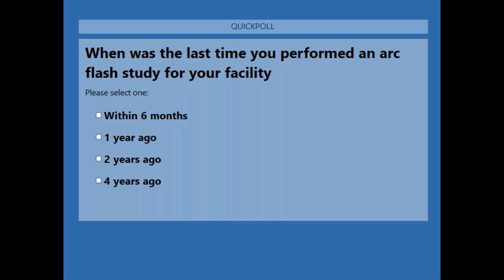Okay, there's one more question that maybe we didn't answer. This is going to be an interesting one. Do the 3 major arc flash software packages have the old and new 2018 standard as selectable options, and therefore the ability to run a comparison? The answer there is yes. The 3 that come to my mind would be ETAP, SKM, and EasyPower. Those all have selectable options between the 2002 version and the 2018 version.